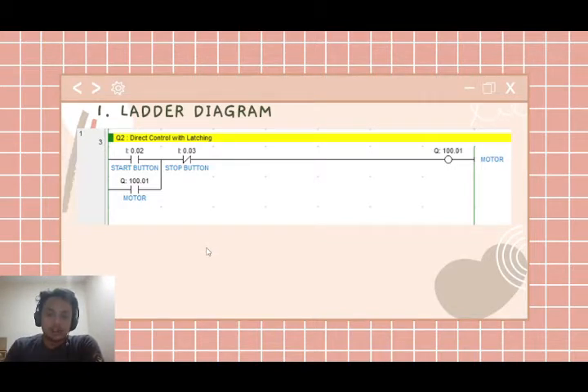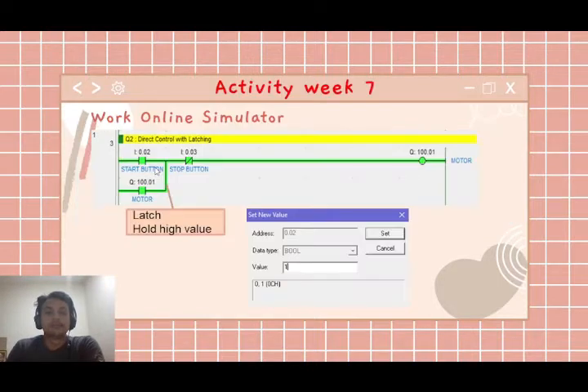The motor will hold the high value, and the function is a latch. If the start button is pressed, the motor output will hold the high value from the start button. This is the operation of direct control with latching when working in the online simulator. If we give the value 1 to the start button, the motor will hold the high value and the output motor will be running.